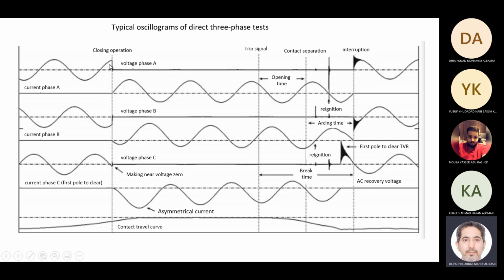This is the voltage and this is the current. When you close it, there will be a current flow. And at this point, a trip signal is given to the breaker, but the breaker needs time to open. So at this point, the breaker contacts start to separate, but the current is still flowing. Why? Because of the arc. Now, at this point, the recovery voltage of the dielectric medium is lower than the voltage, so the arc is reignited and the current is still flowing, until this point where the recovery voltage is higher than the voltage, then the current is stopped.